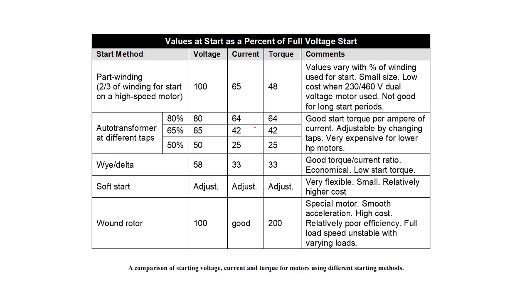The line side of the auto transformer, or the utility side of it, is where we experience a double reduction. So if I knew the normal inrush current of that motor, and I wanted to know how much current is going to be on the supply of the auto transformer, I could take my 80% squared, which is 64%. So we could have down to 64% on the 80% tap, roughly 42% on 65%, and 50% is 25%. Torque, also, the produced torque is proportional to the square of the percent voltage reduction. So if I reduce the voltage to the motor to 80%, 0.8 squared means that I'm only going to have 64% of the normal starting torque during reduced voltage starting. And same thing, 42% for a 65% tap and 25% of the normal starting torque using a 50% tap.